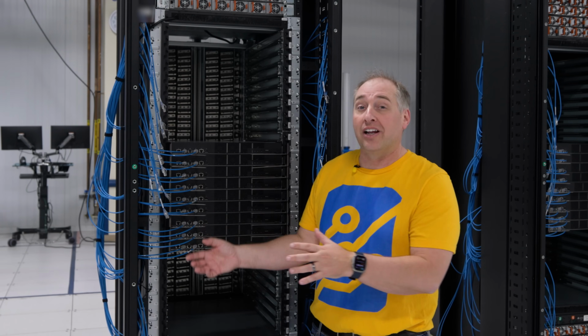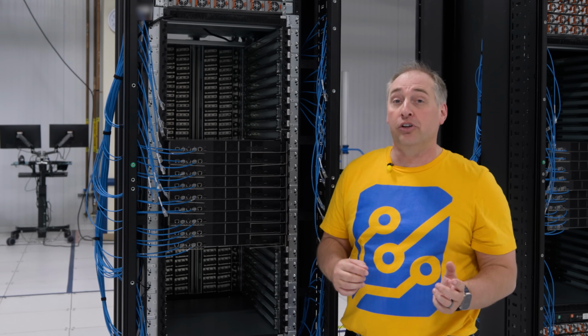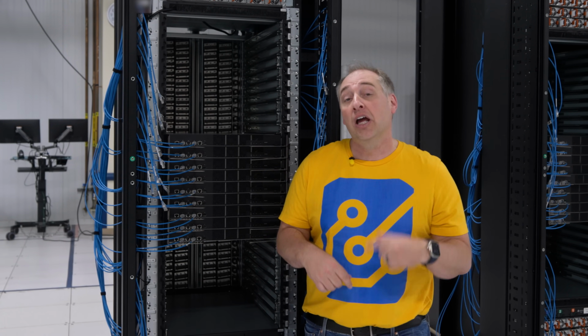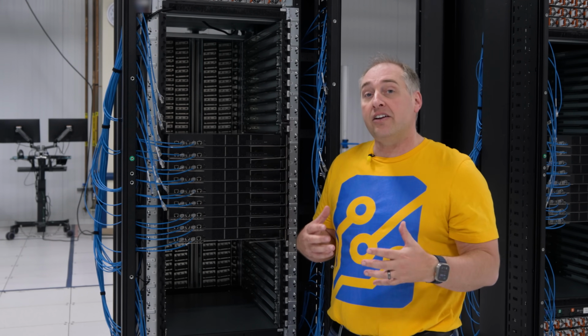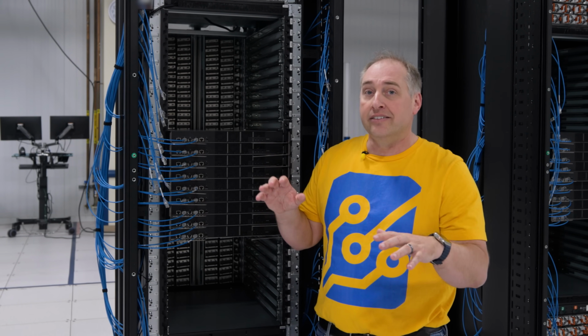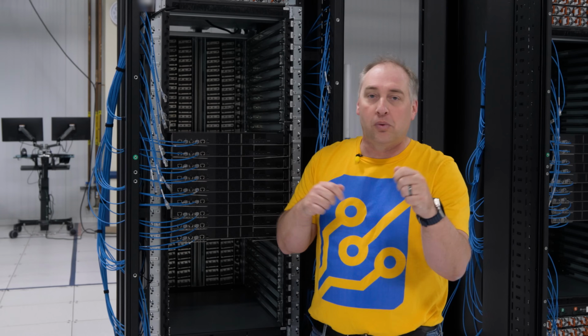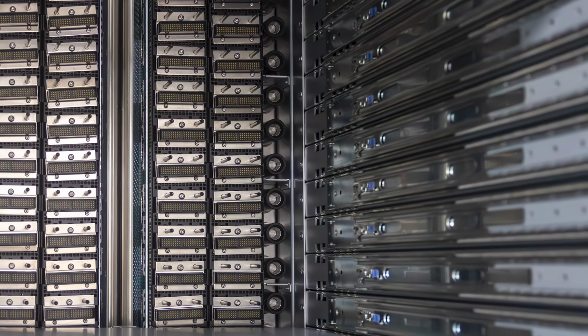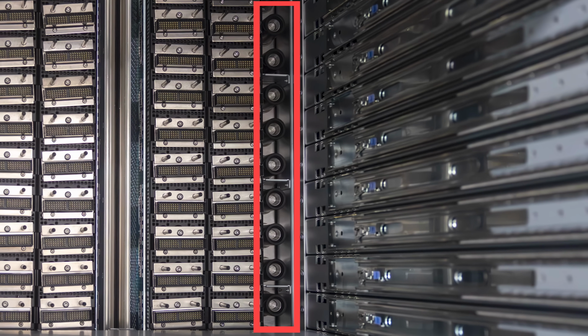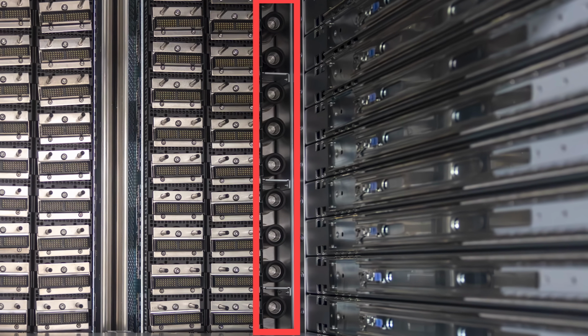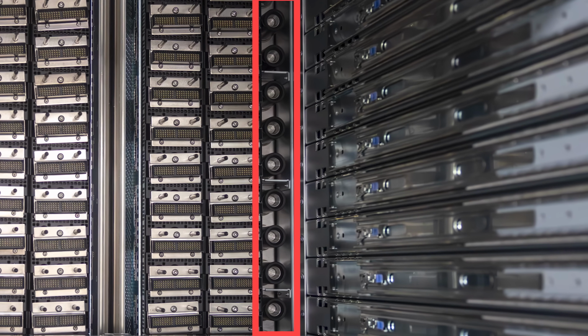Another big feature whenever you connect the NVLink switches or the compute nodes into this backplane is not just the data or the power connectivity, but also the cooling. Instead of having liquid cooling that is designed to go into each individual one that you have to go in and plug in individually, like we've seen on previous generation designs, this has the liquid cooling manifolds in the rear with quick disconnects. There's both a hot and a cold side to the quick disconnects.